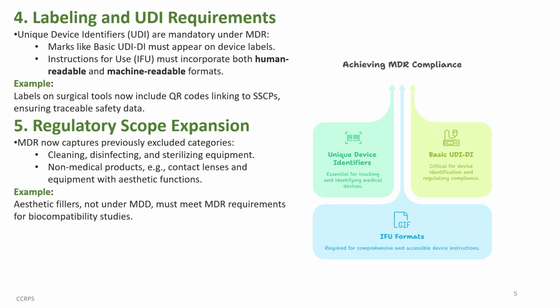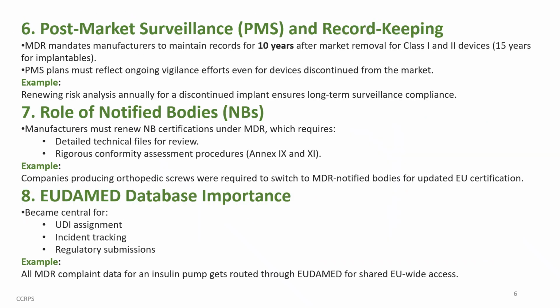Regulatory scope expansion. MDR now captures previously excluded categories: cleaning, disinfecting, and sterilizing equipment, and non-medical products, for example contact lenses and equipment with aesthetic functions. For example, aesthetic fillers not under MDD must meet MDR requirements for biocompatibility studies.